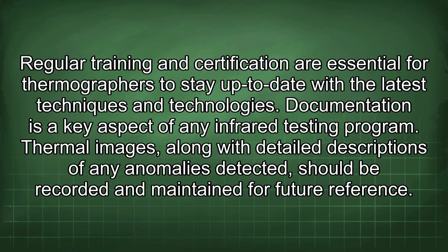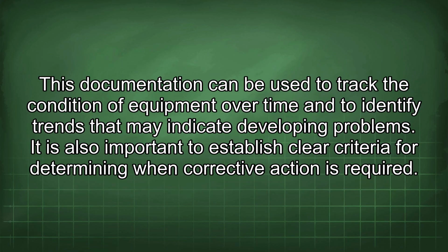Documentation is a key aspect of any infrared testing program. Thermal images, along with detailed descriptions of any anomalies detected, should be recorded and maintained for future reference. This documentation can be used to track the condition of equipment over time and to identify trends that may indicate developing problems. It is also important to establish clear criteria for determining when corrective action is required.